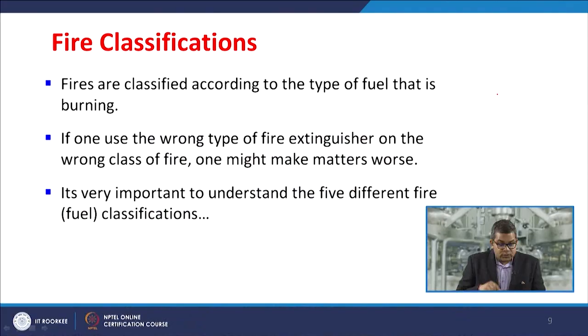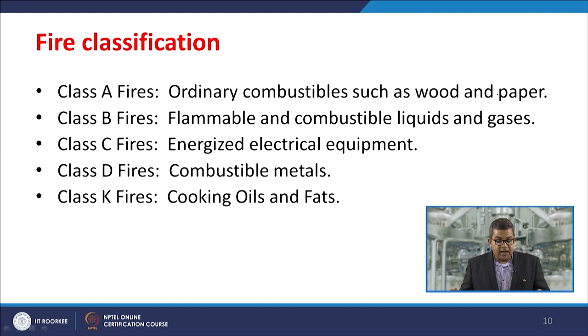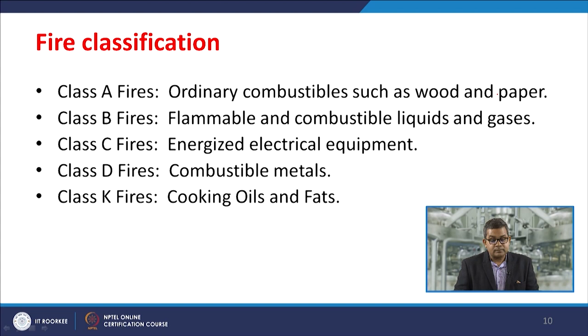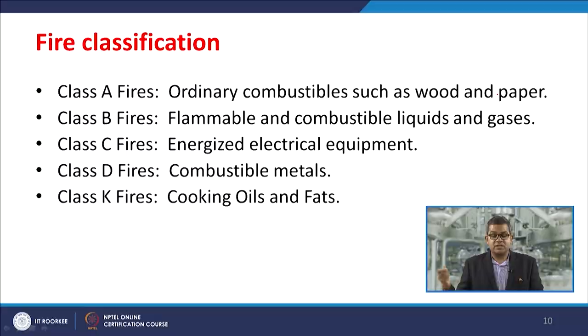It is very important to understand the different classes of fire. There are five different classes: Class A — ordinary combustibles such as wood and paper, extinguishable with normal water; Class B — flammable and combustible liquids and gases; Class C — energized electrical equipment, where water cannot be used as it will propagate the hazard; Class D — combustible metals; and Class K — cooking oils and fats.